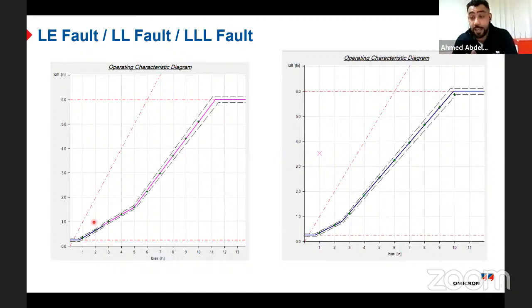parameter testing. I'm testing now the parameters I have entered to the relay: slope, CT ratio, polarity, the harmonics content, the rated power, the rated apparent power, the rated voltage. These parameters I entered. But am I sure that if I install this relay in this system, the relay will trip correctly or not? Here, I need to think beyond the parameters, to the performance test.